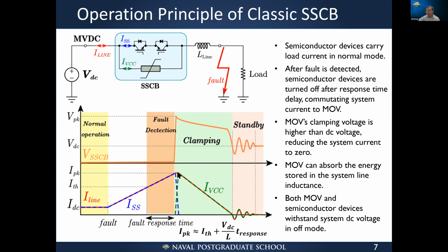The MOV will pick up the current. The MOV is kind of a resistance. Once the current flows through the MOV, the MOV will generate a high voltage. We say it's clamping voltage, and this voltage is higher than the system DC voltage. So you get an effective voltage across the line inductance that starts to drive the fault current down. And during this process, as you can see, the MOV is withstanding high voltage and also carrying high current. So during this clamping stage, the MOV is absorbing energy.